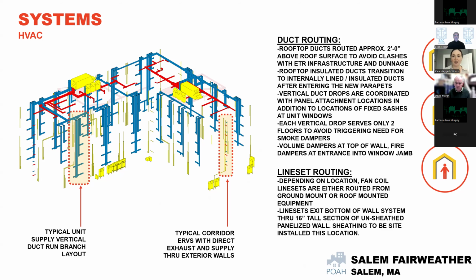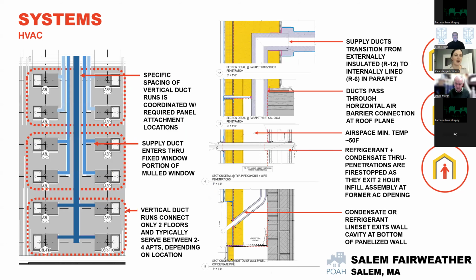I'll go through this quickly since we're probably running out of time, but the image on the left is the most helpful. Again, related to not being able to have smoke dampers, what that meant for us here was we can only connect 2 stories at a time by code. In an ideal world, we probably could have run one big wide duct and just hopped off at every unit and done it that way.